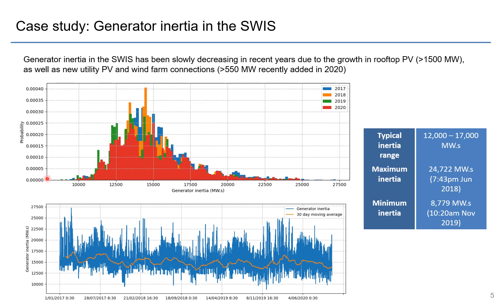We tracked large synchronous generator inertia in the SWIS, and it's been slowly trending downwards in recent years — primarily due to growth in rooftop PV as well as new utility-scale PV and wind farms. The histograms from different years show inertia usually in the range of 12,000 to 17,000 megawatt seconds. The blue curve from 2017 is shifted to the right, meaning we had more inertia then. As the years passed — 2018, 2019, 2020 — there's a slight shift to the left, toward lower inertia, with the lows getting lower and the highs less high. We've reached minimum inertias of around 8.8 gigawatt seconds.